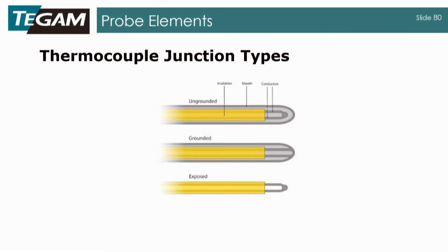So next we have the thermocouple junction types. And here are the three different types. Basically, just to show you here, this on the outside is going to be your sheath, which is usually going to be stainless steel. These two wires on the inside are your thermocouple conductors. And then this is the insulation, one type of insulation, that's going to insulate your thermocouple wires from the outside sheath. Now, this first type here is ungrounded, and the reason it's called ungrounded is because your thermocouple elements are insulated from the sheath.